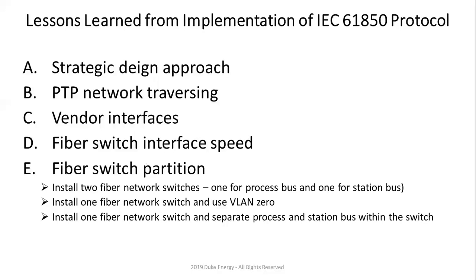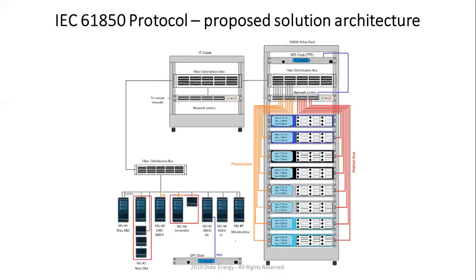So if you wanted to see how this works, okay, here we go. This is essentially how this solution works, right? On the bottom left, you have different merging units. And I have put which merging units actually have 100 M and which merging units have 1 gig, because remember, you have to size it with that. Merging unit number 5, I told you that all the merging units take PTP clock. Merging unit number 5 is the PPS.